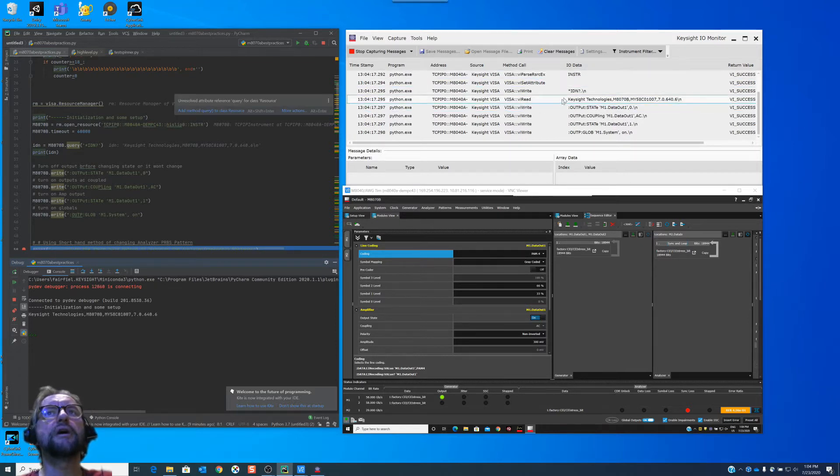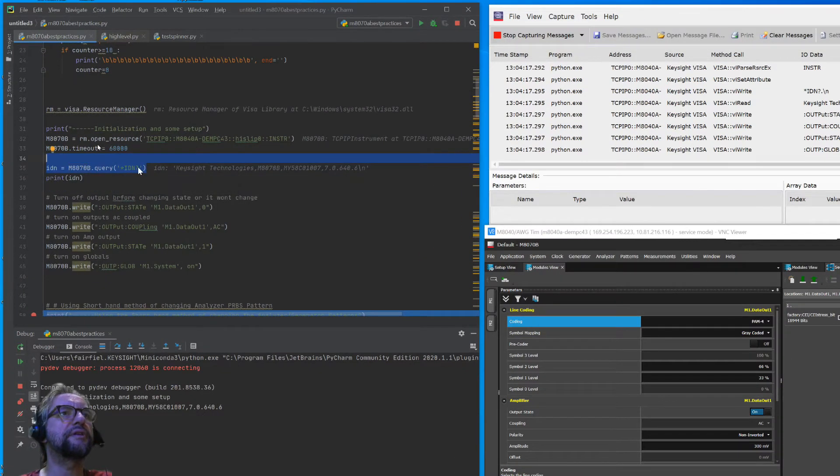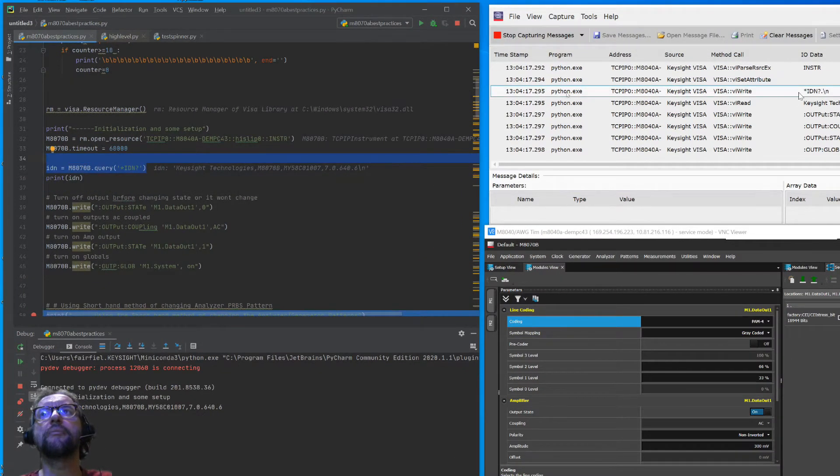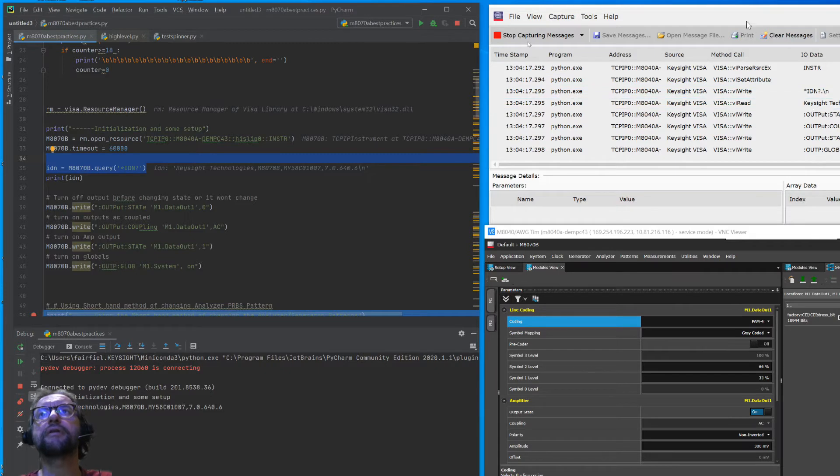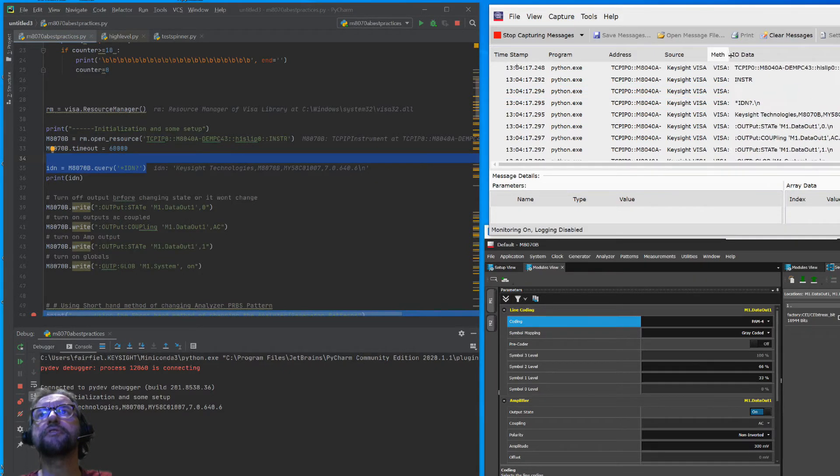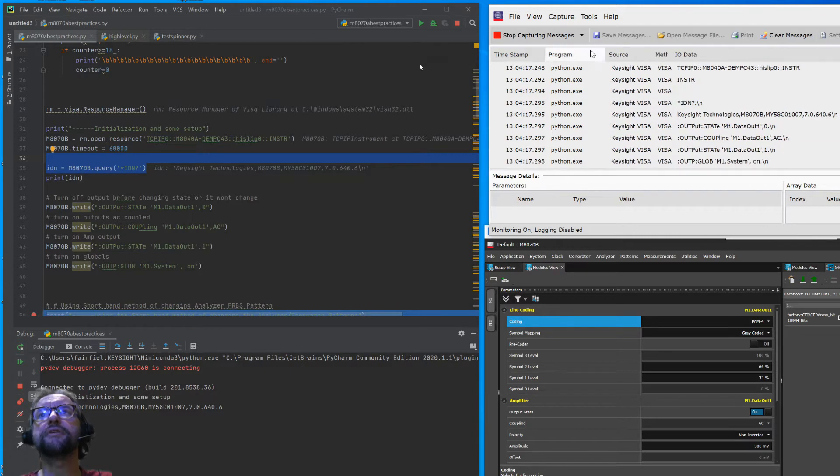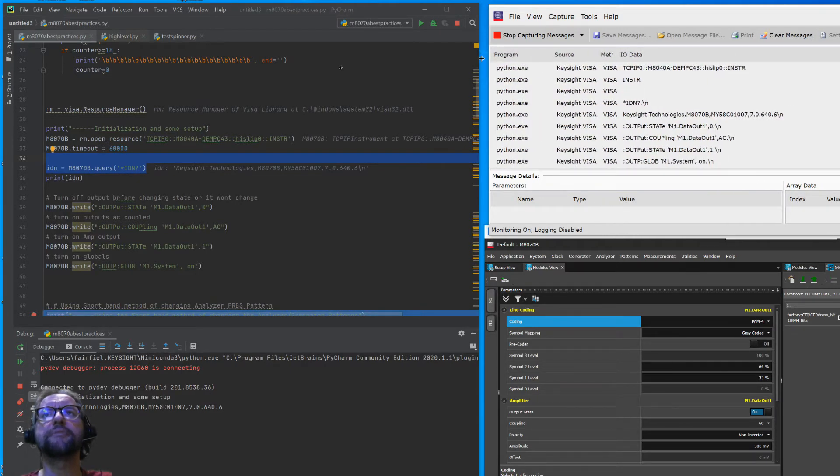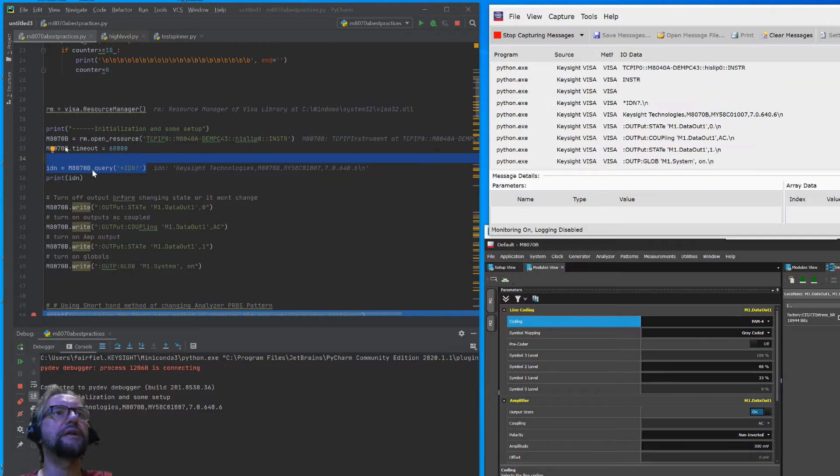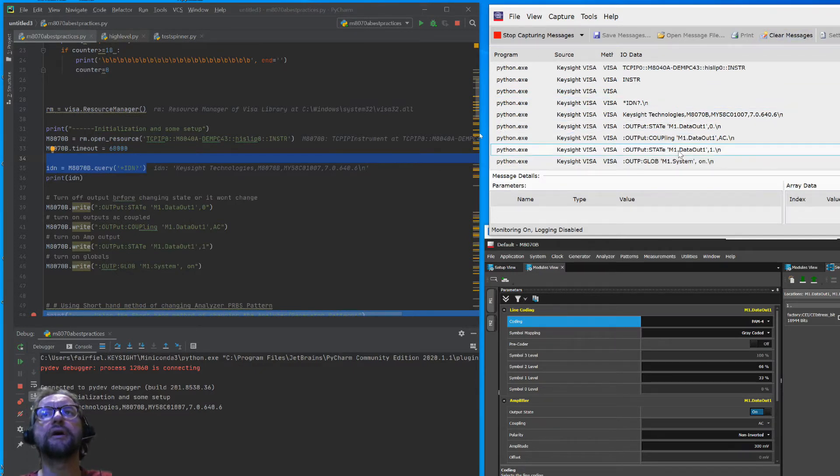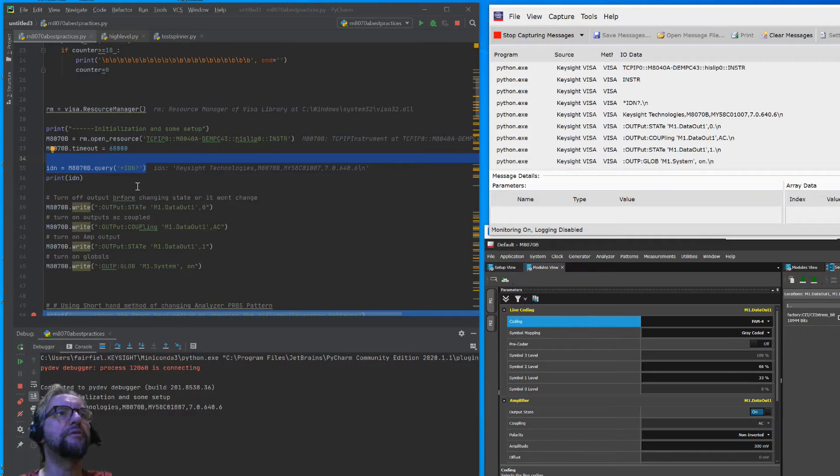So we've gotten as far as running a few of these commands. So let's see what happened. I connected and attached the instrument. And then I sent the IDN query, which is right here. We've got the IDN query. Let's just move these method calls, because we don't care so much about what those are. Let's just squish these a little bit. So it'll make it easy for the presentation here. And we see the program that called it is Python. But here we go. Now we've got the IDN, data out, zero, coupling, global system on, new line. And I'm also printing this out to the window. When I did get the query, I print the IDN here. So that's how that works.